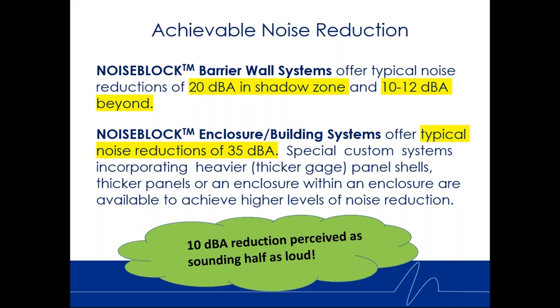We can tune them if you need 55 dBA. Now, you might ask what these dBA numbers actually mean. It's a logarithmic scale, and a 10 dBA reduction will be perceived by the average human as sounding half as loud. So if something is at 100 dBA and you reduce it only 10 dBA to 90 dBA, that doesn't seem like much, and it may still not be quiet enough per OSHA standards, but you'll perceive it as half as loud as before.